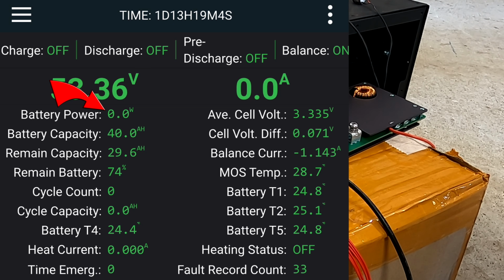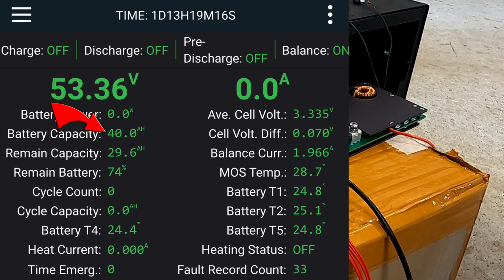Battery power in watts, the average cell voltage, and battery capacity is 40 ampere hours - I have to set this correctly. Cell voltage difference is 70 millivolts. Remaining capacity is all calculated by the BMS, and we can see the balance current - the balancer is actually active at the moment, probably because of wrong settings. Remaining battery capacity is 74%.